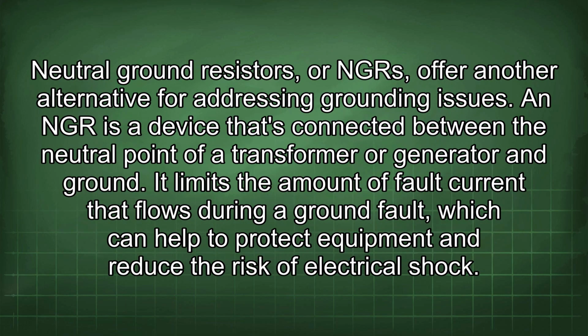Neutral ground resistors, or NGRs, offer another alternative for addressing grounding issues. An NGR is a device that's connected between the neutral point of a transformer or generator and ground. It limits the amount of fault current that flows during a ground fault, which can help to protect equipment and reduce the risk of electrical shock.